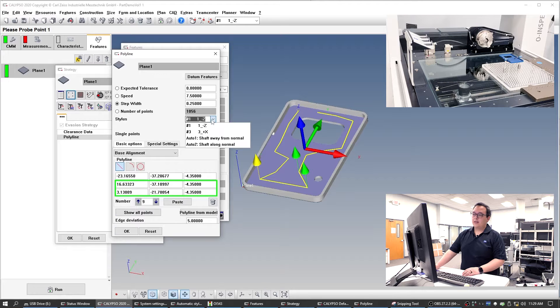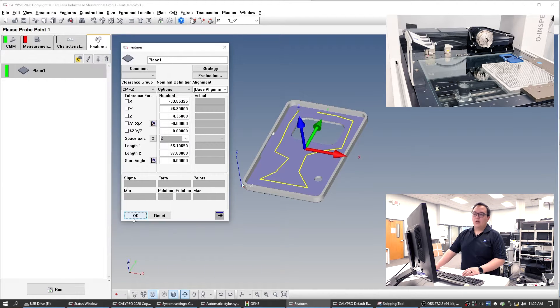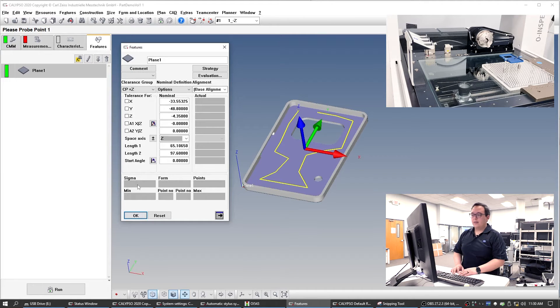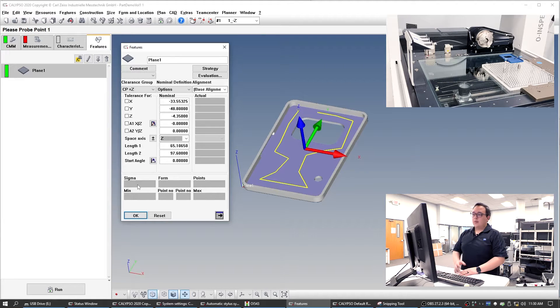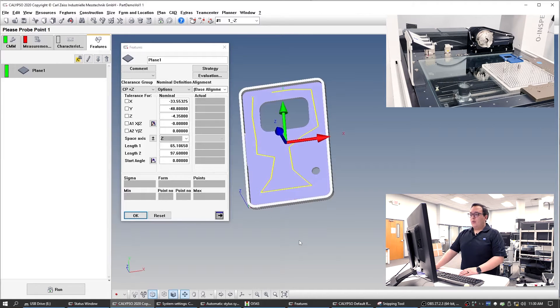Our stylus here: 1_minus_Z. Perfect. Now we need — this is going to be our primary base alignment feature, and so this is going to take care of our wobble. Something we want to do is we want to clock this — make sure that it's not rotating in what would be the Z axis. We can do that with one or two lines. Let's pick the top line, and we'll do it with the same probe. So let's define a line on this plane.